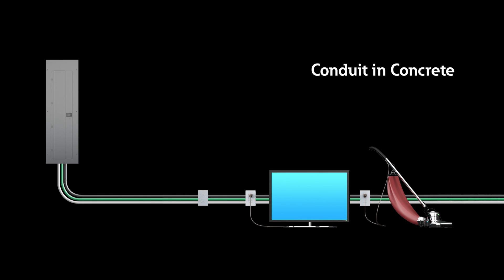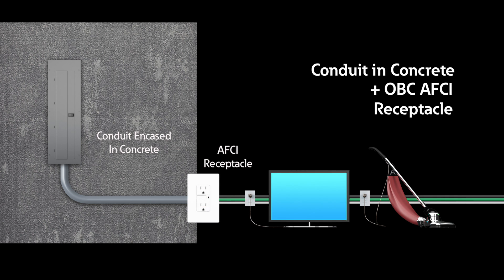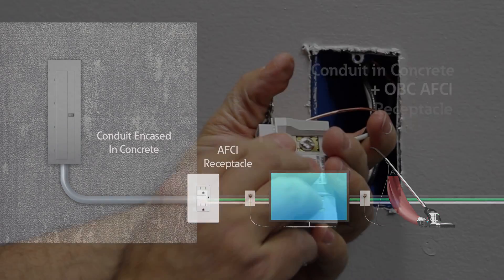The code also allows the use of conduit in concrete with an AFCI receptacle. This method allows for metal or non-metallic conduit or tubing to be encased in not less than 2 inches of concrete for the portion of the branch circuit between the panel and the first AFCI receptacle in a circuit. This method has limited applications and can be costly.